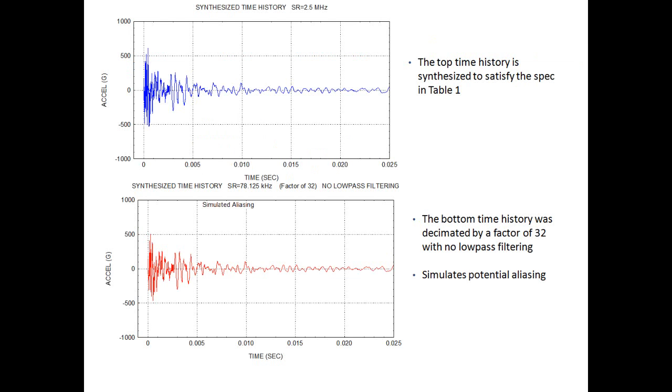And it's sampled at 2.5 megahertz. Well, as you recall, the final breakpoint in table 1 was at 250 kilohertz. So this is 10 times higher. And the waveform is carefully controlled so that there are no energy components above 250 kilohertz. So we're going to say that this blue curve is the true data. It represents the true analog data with no aliasing error.